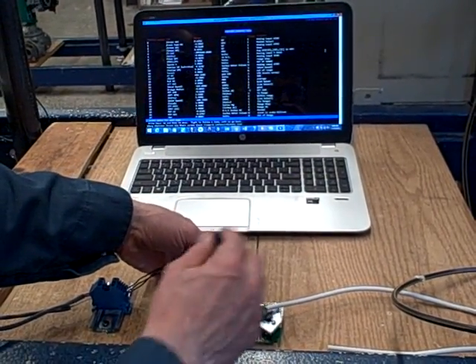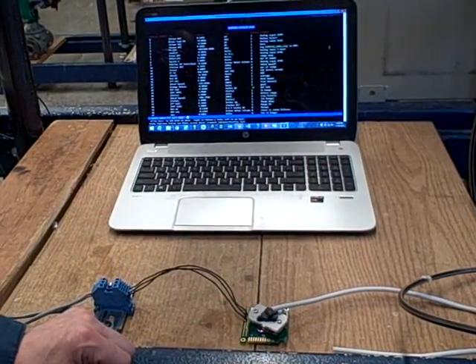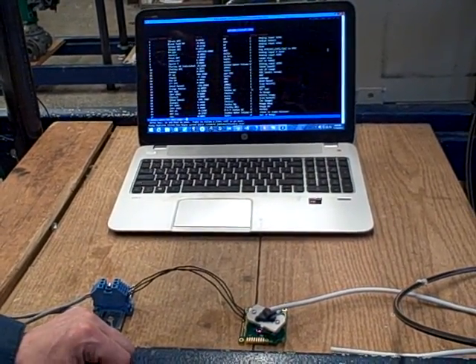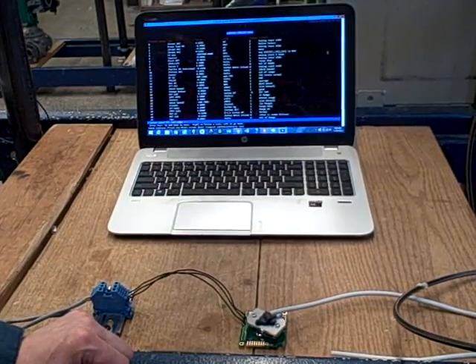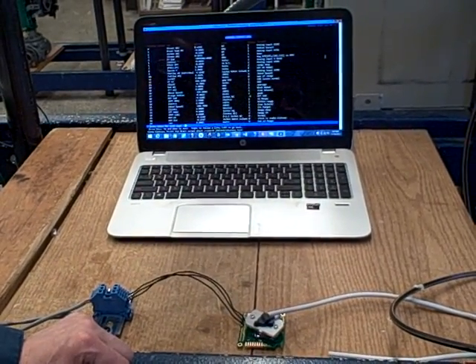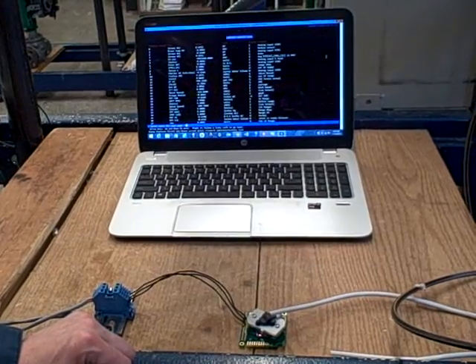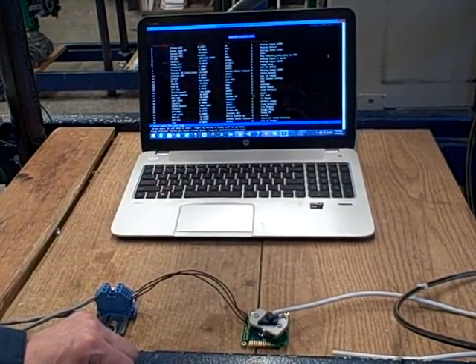And of course, the soldering of wires, the reading of the manuals, and the configuration of the unit. Students have to figure out which pins to jumper to do a zero calibration and a span calibration. It's all kinds of learning packed into this one fairly affordable and small CO2 sensor. Thank you.